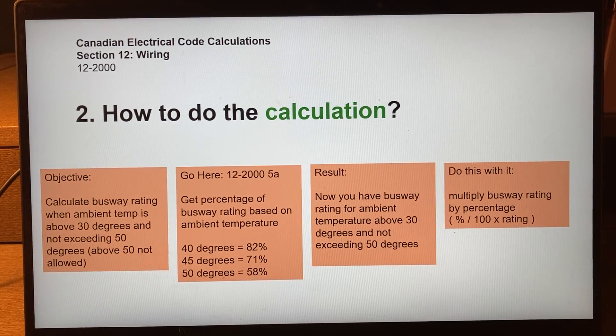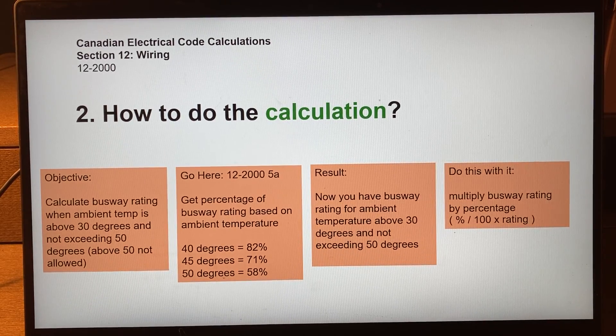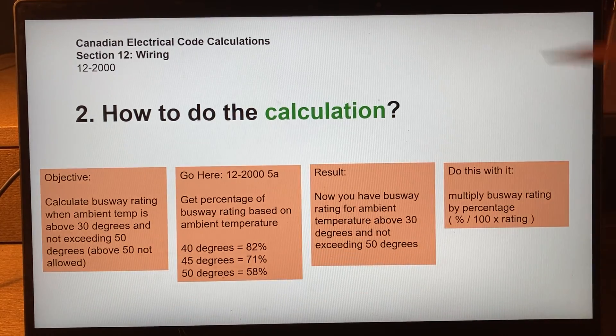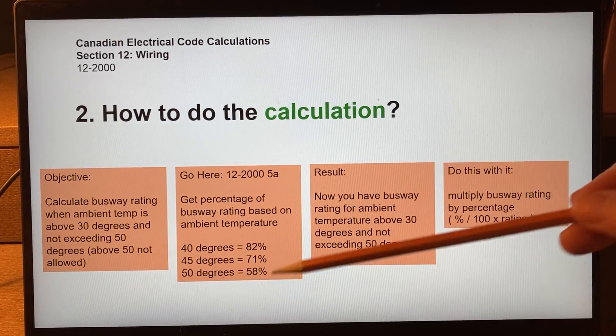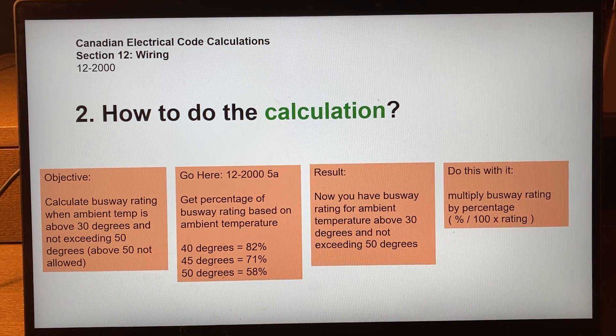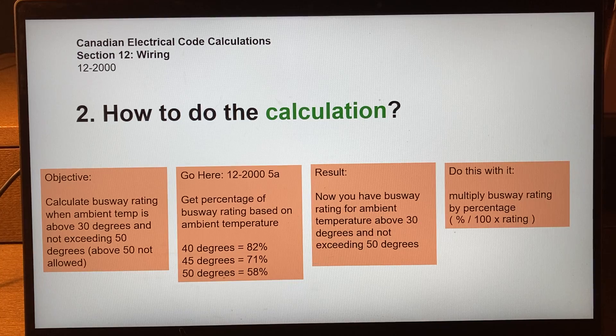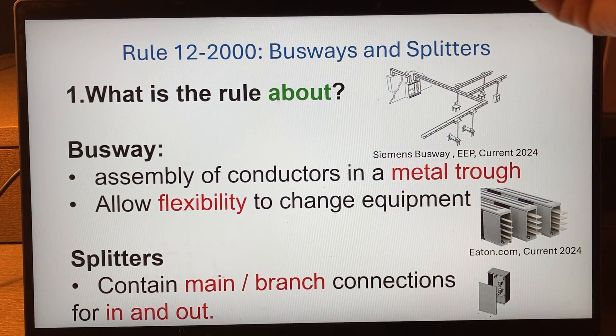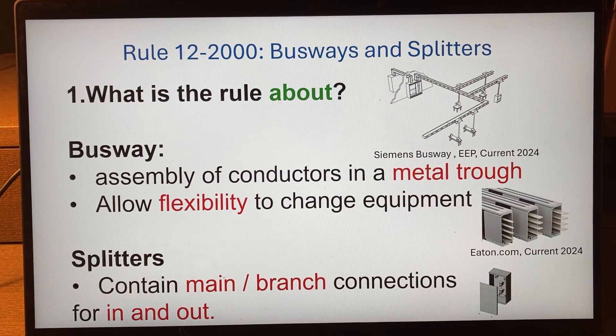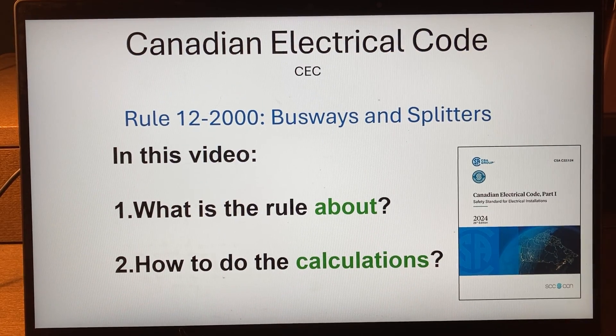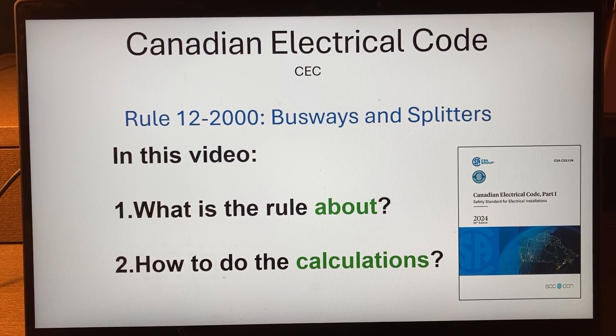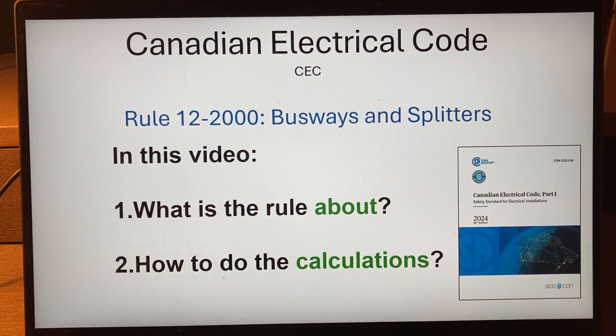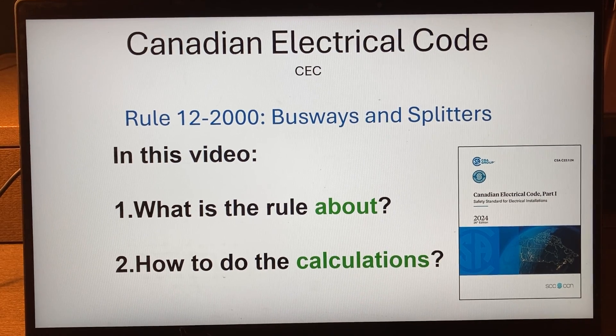Sub-rule 1 said you always have to mount a busway in an accessible place, except if you follow sub-rule 5. Sub-rule 5 says that if you de-rate it, you can put it inside a drop ceiling, which is a very common installation. I hope that has been useful — that was rule 12-2000, busways and splitters in the Canadian Electrical Code. Comment below: is this useful to you? Which other calculations would you like to see? I'd like to make a video about every one of them so you can easily pass your exam.